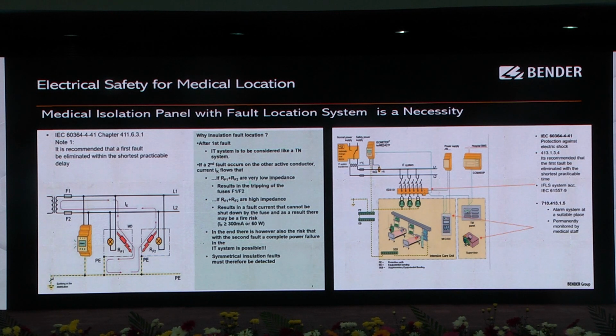We have 2 types of solution: one without fault location and one with fault location. Without fault location means it will only show the insulation value going down. Then you have to identify one by one, during operation or after operation, by switching off one by one. With fault location, it will tell immediately whenever your surgery is going on, so you can identify online. So the maintenance team, technician or nurse can understand which biomedical equipment is faulty. Then they can immediately go and identify the fault, remove the biomedical equipment, and hand it over to the biomedical team. So we have two solutions.